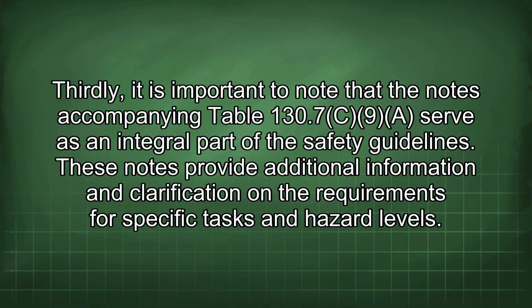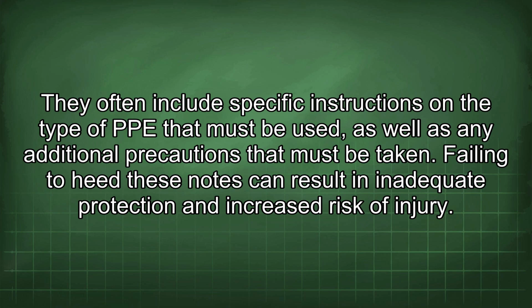Thirdly, it is important to note that the notes accompanying Table 130.7 serve as an integral part of the safety guidelines. These notes provide additional information and clarification on the requirements for specific tasks and hazard levels. They often include specific instructions on the type of PPE that must be used, as well as any additional precautions that must be taken. Failing to heed these notes can result in inadequate protection and increased risk of injury.